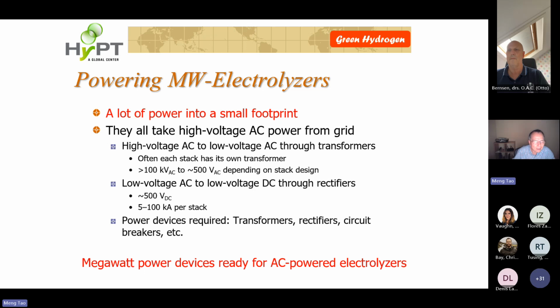Then we do rectification to convert the low voltage AC power, typically around 500 volts, to DC power. But the current is enormous, and 100,000 amps per stack is often what you can see.